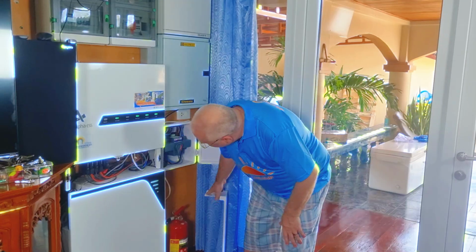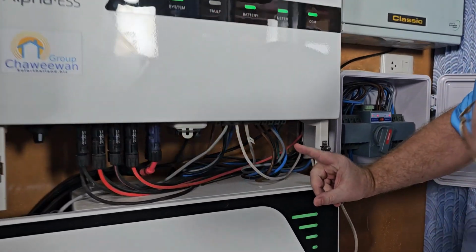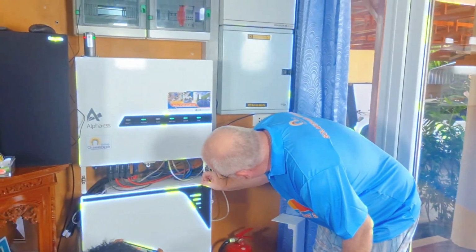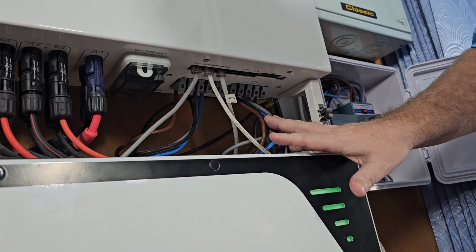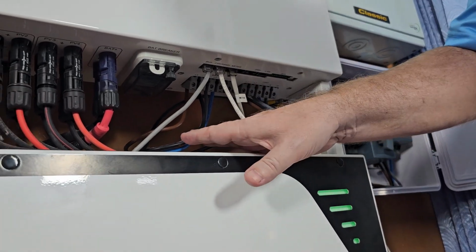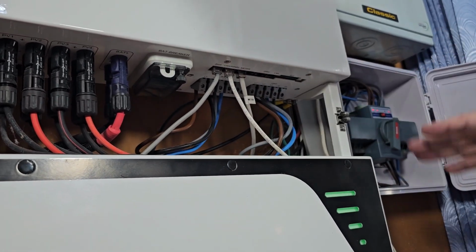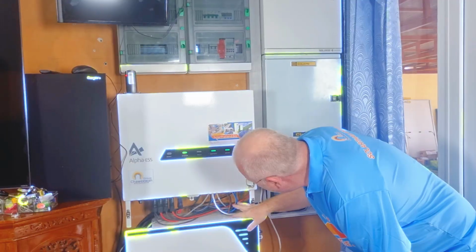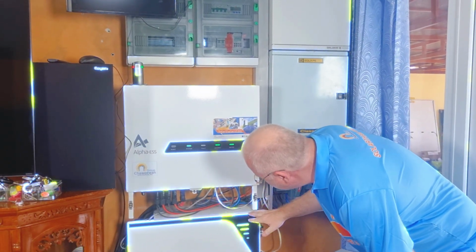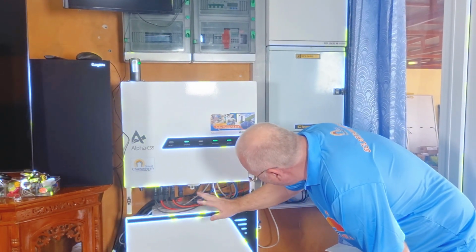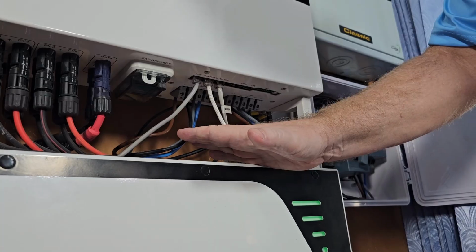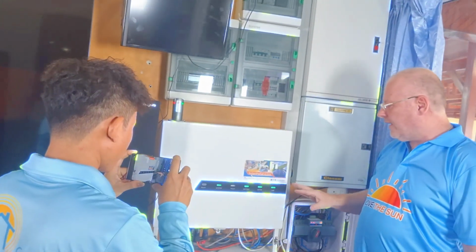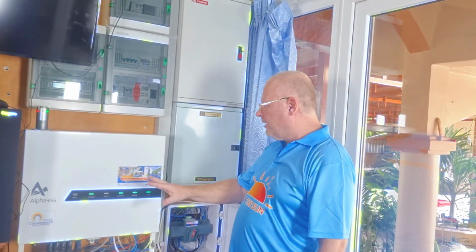We have two outputs of electricity from this inverter, and all hybrid inverters. You have the backup and you have the grid. So when there is a power cut, the inverter switches and stops output here and only has output on the backup side. So the backup side is not connected to the grid and gives then power to the UPS panel. So that is why a hybrid inverter has two outputs. One is being used when the grid is up, one is being used when the grid is down, the backup side. So that's why inside here you actually have 6 inverters.